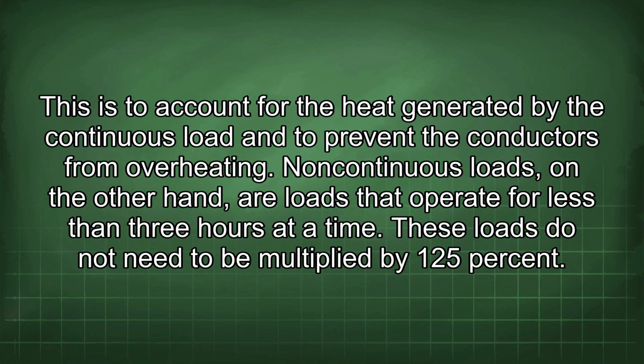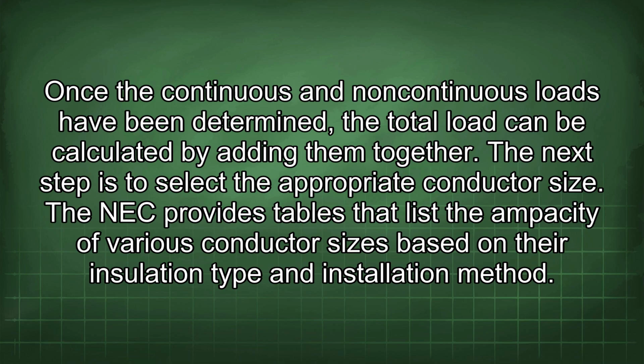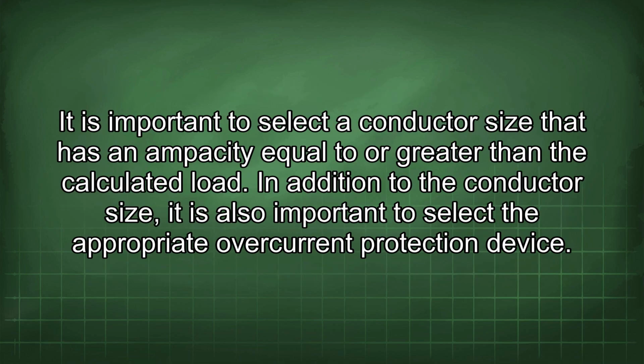This is to account for the heat generated by the continuous load and to prevent the conductors from overheating. Non-continuous loads, on the other hand, are loads that operate for less than 3 hours at a time. These loads do not need to be multiplied by 125%. Once the continuous and non-continuous loads have been determined, the total load can be calculated by adding them together. The next step is to select the appropriate conductor size. The NEC provides tables that list the ampacity of various conductor sizes based on their insulation type and installation method. It is important to select a conductor size that has an ampacity equal to or greater than the calculated load.